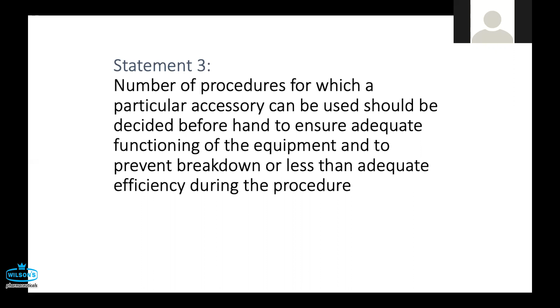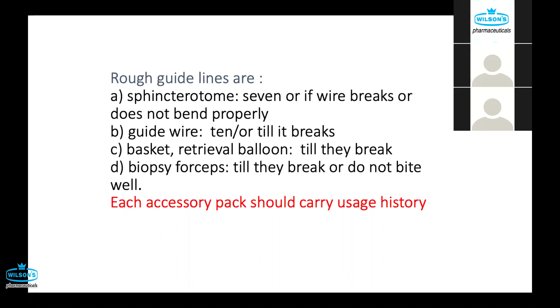Sphincterotome: 7 times, or until the wire breaks or does not bend properly. Guide wire: 10 times, or till it breaks. The only problem is that the tip of the hydrophilic wire may break inside and stay there, and that's the reason you have to put a limit on the number of times. Baskets and retrieval balloons will not cause any harm, except that they will delay the procedure, so they can be used till they break. Biopsy forceps: till they break or do not bite well. Each accessory pack should carry a usage history, showing how many times it has been used.